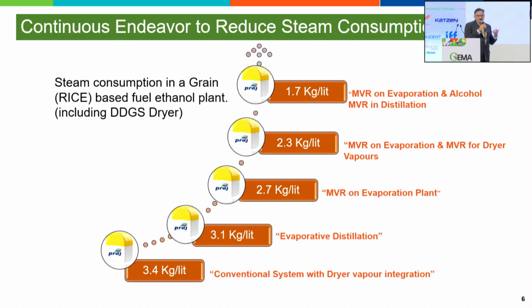To further save steam, there's a technology called evaporative distillation, which reduces steam consumption from 3.4 to 3.1 kg per liter. For further saving, there's MVR technology used in the evaporation plant, which further reduces steam consumption to 2.7 kg per liter. Then you have the option of using MVR both in the evaporation plant and on dryer vapors, which reduces steam consumption to about 2.3 kg per liter.